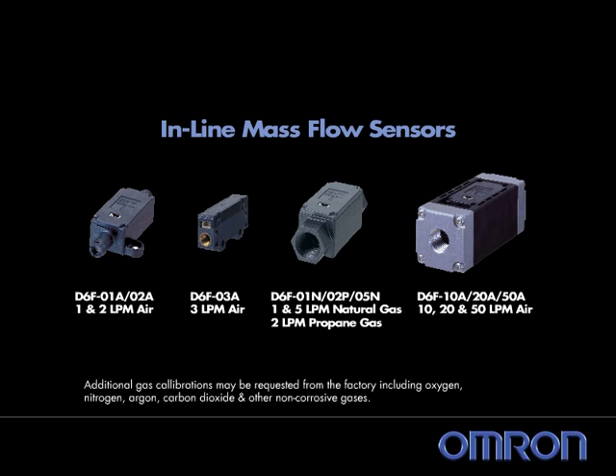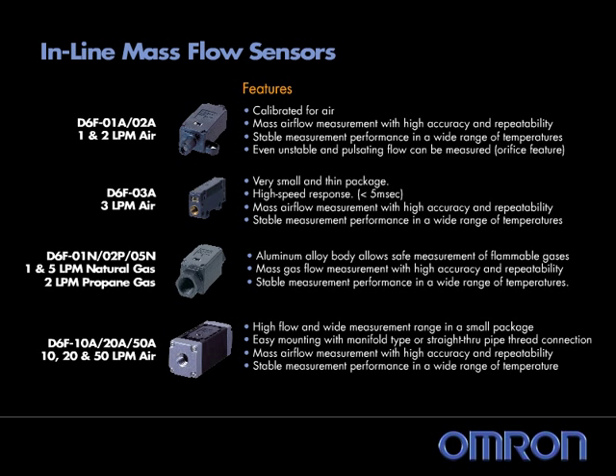Models are available from 1 to 50 LPM. The D6F0102 series has barbed ports for quick installation and an output side orifice to stabilize pulsating flows. The D6F03 has the smallest overall package size and fastest response time of the product lineup. The D6F05 is made of an aluminum alloy body for natural gas and propane applications. The D6F102050 is the largest package with multiple port options.